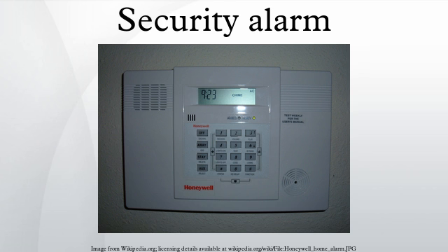More typical systems incorporate a digital communication unit that will contact the central station via the public switched telephone network and raise the alarm either with a synthesized voice or increasingly via an encoded message string that the central station decodes. These may connect to the regular phone system on the system side of the demarcation point, but typically connect on the customer side ahead of all phones within the monitored premises so that the alarm system can seize the line by cutting off any active calls and call the monitoring company if needed. A dual signaling system would raise the alarm wirelessly via a radio path or cellular path using the phone line or broadband line as a backup, overcoming any compromise to the phone line.